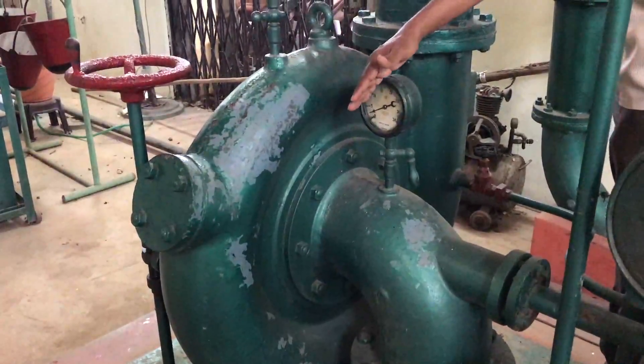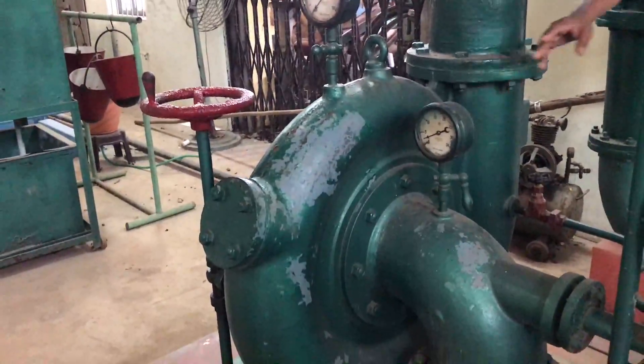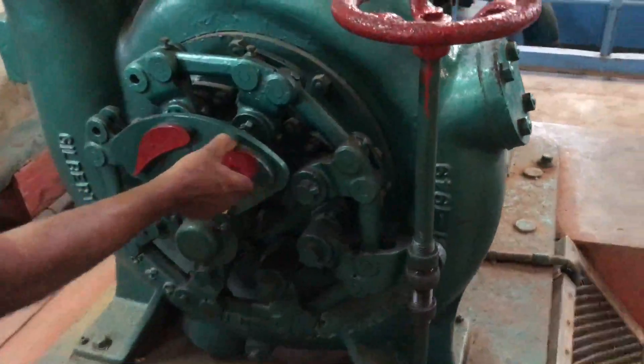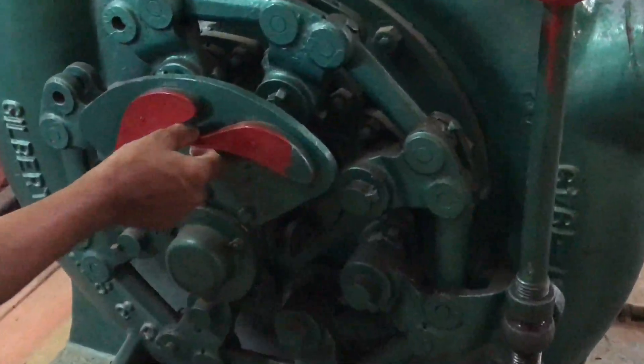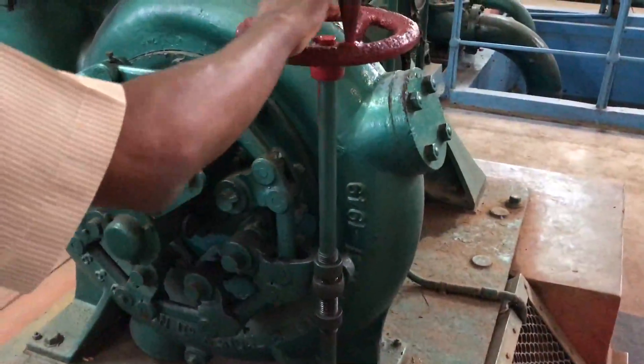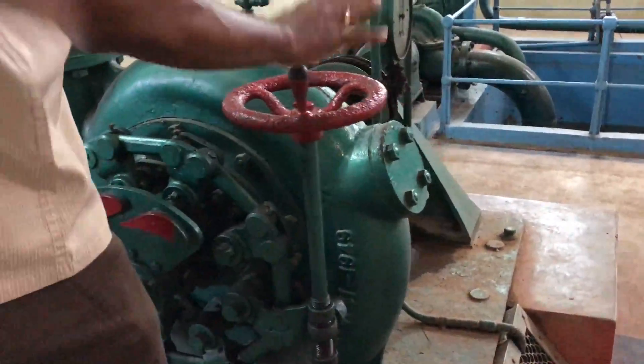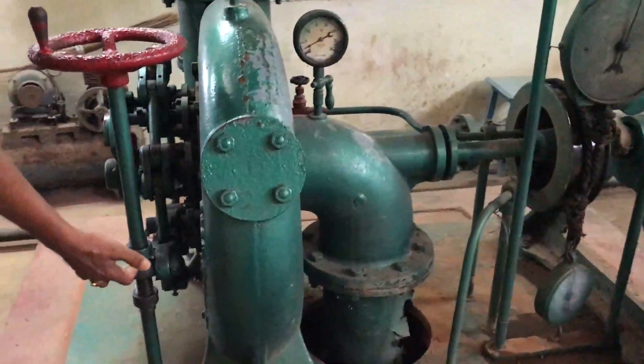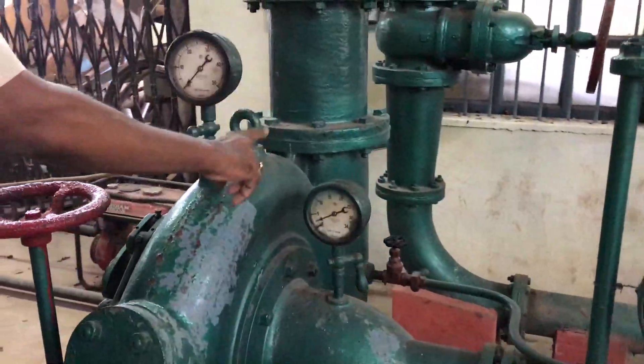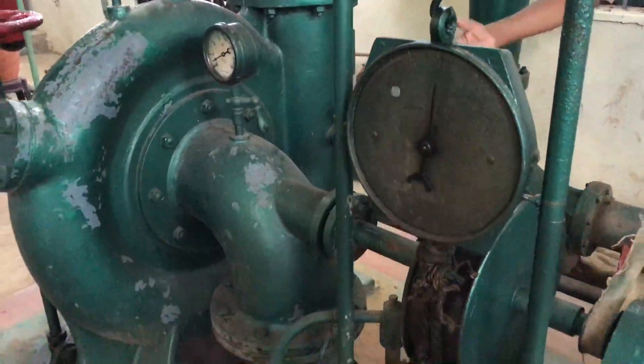The number of stay vanes is half the number of guide vanes. Normally there are 12 guide vanes and 6 stay vanes. To control the quantity of water entering the turbine, the gap between the guide vanes is adjusted. A threaded screw mechanism with a handwheel changes this gap. In the performance test, the screw is given three and a half rotations.